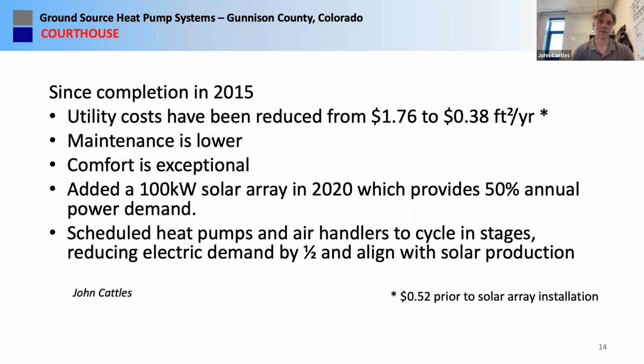We've also been able to utilize the distributed nature of the heat pumps to try to match our energy load to our energy production with the solar array. So we're experimenting with staging heat pumps to cycle on and off, so they're not all cycling on at one time and creating a high demand charge. We're staging those in a way that's flattened our demand curve and worked nicely with our solar production.